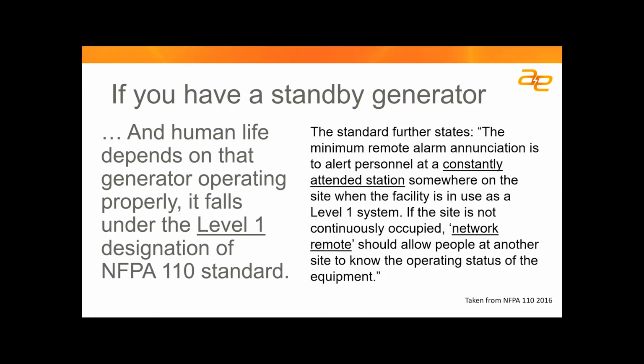When it comes to the actual operation of the equipment, the standard further states that if you have a generator that falls into that category, you have to annunciate critical alarms in a location that is constantly attended. If it's not, you have to network that control panel to a location where people will always know the operating status of that equipment.